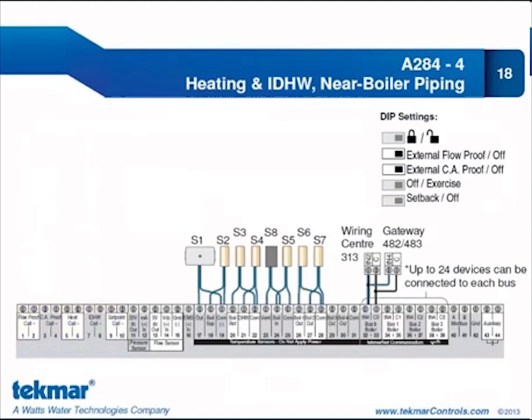Now we're not doing flow proof, we're not doing combustion air proof, so it makes sense that those call terminals are empty. You'll notice too that the dip switches for external flow proof and external combustion air proof are in the off position. We are doing space heating, so why are the space heating call terminals empty? That is because we are communicating the heat call through tekmarNet, and we'll talk about that more in a minute. We are doing indirect domestic hot water, but we're using a sensor, not an aquastat, so these call terminals are also empty. And we're not doing set point load, so we have nothing to connect the set point call terminals to.